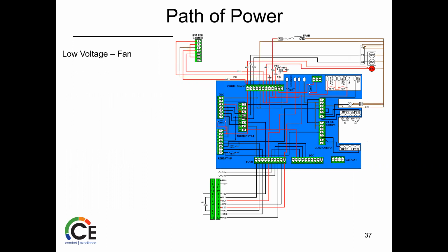All right, so fan operation. Obviously G, if we're just running the fan, we get 24 volts to G. We're going to look and make sure that jumper is intact. We can undo that if we've got some sort of relay or something in there.